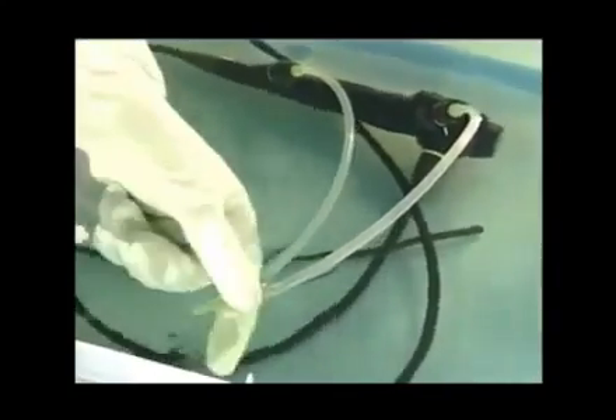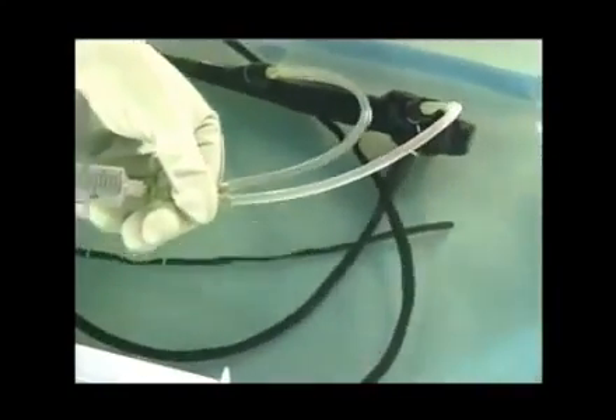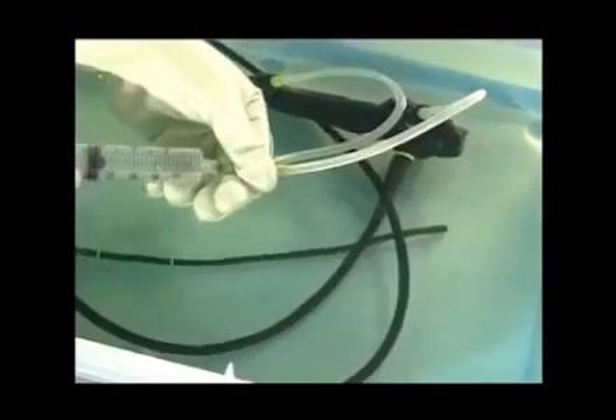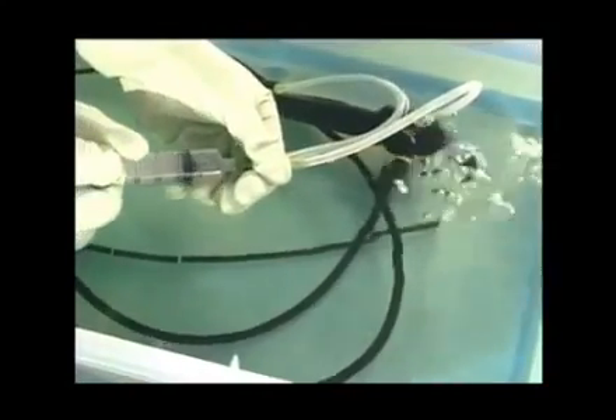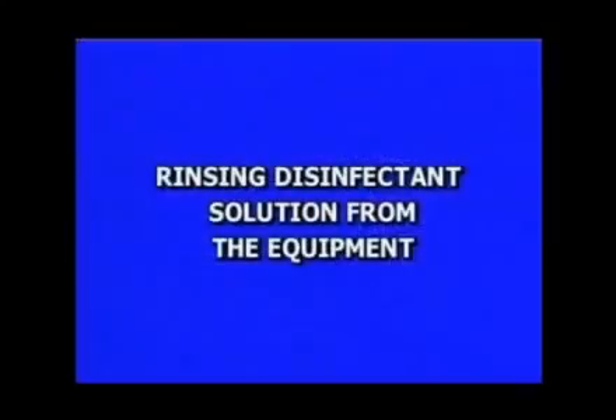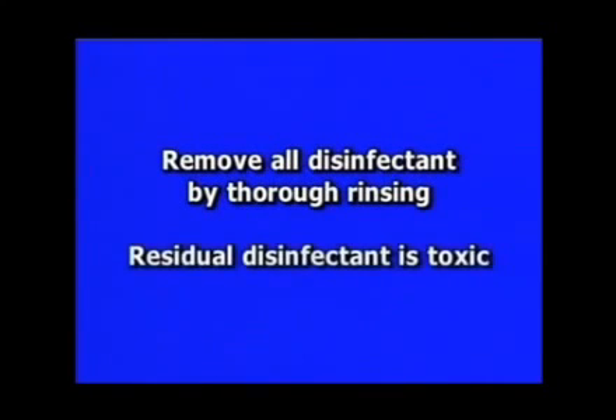Connect a sterile 30 cc syringe to the adapter and inject air to remove all disinfectant solution from the channels. The next step is rinsing. It is very important to remove all disinfectant solution from the bronchoscope. Residual disinfectant is toxic and can injure the next patient examined with the equipment.